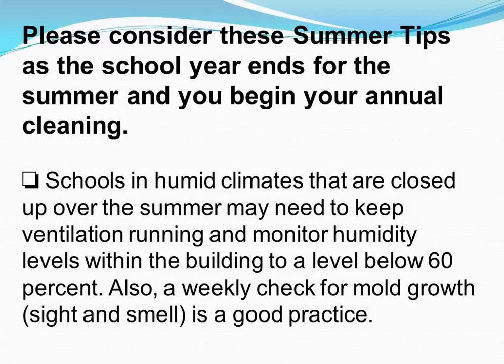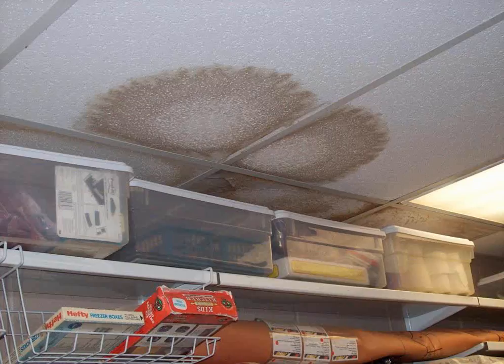Yes, it is. And here's a picture of stained ceiling tiles. You can see there's probably maybe a roof leak here. Who knows how extensive that mold problem is in the plenum, above the ceiling tiles. And then you have maybe water dripping down, who knows, inside the wall. A big concern about mold is hidden mold, which you really can't see. So that's a big issue.